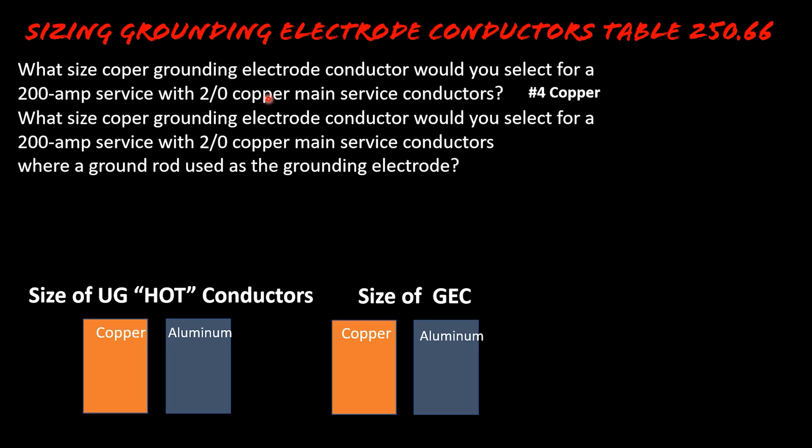Now let's look at this question: what size copper grounding electrode conductor would you select for a 200 amp service with 2/0 copper main service conductors, where a ground rod was used as the grounding electrode? So immediately you're like, 'Boom, I got this — I head to Table 250.66.' This is where the breakdown happens. I'm going to give you some simple tips so you know how to raise red flags when you're in the testing center or out in the field.